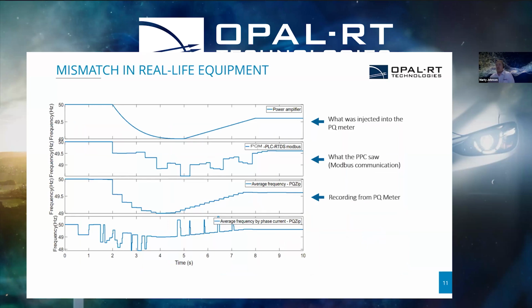Let's have a look at an example that we've come up with, and we've seen this on site, and it's a test that we did back in the lab. On the top is the signal that we injected through the power amplifier. We're changing the grid frequency in this instance. At the start, we're doing a rate of change, and the second graph is what the PPC actually saw. You can see that the second graph definitely doesn't match the first; it's all over the place.